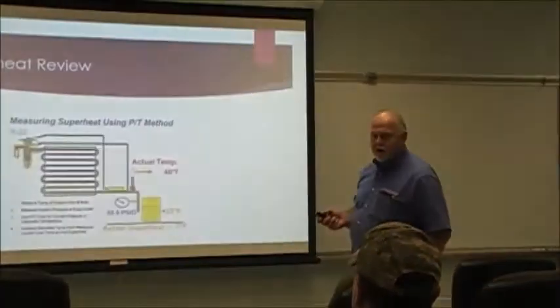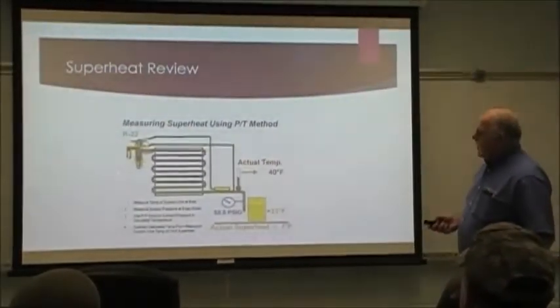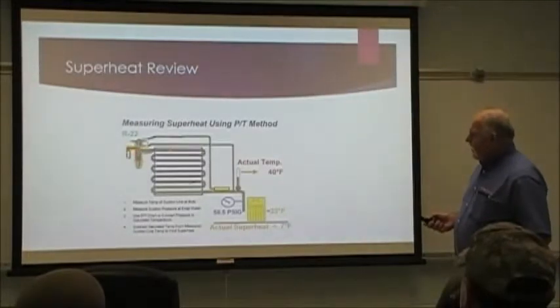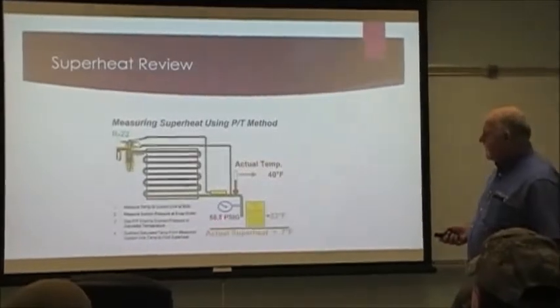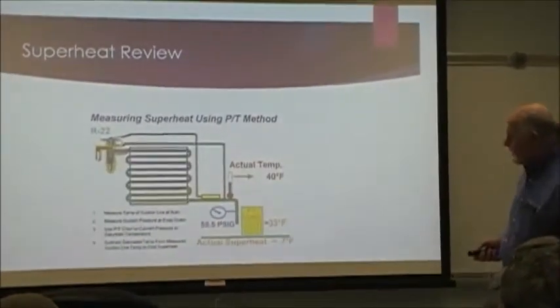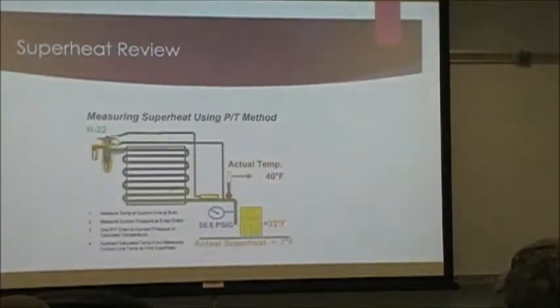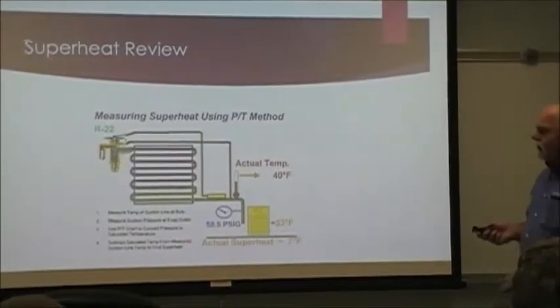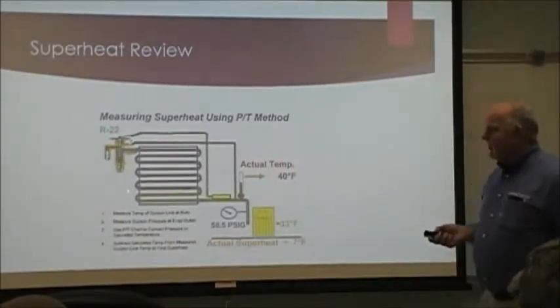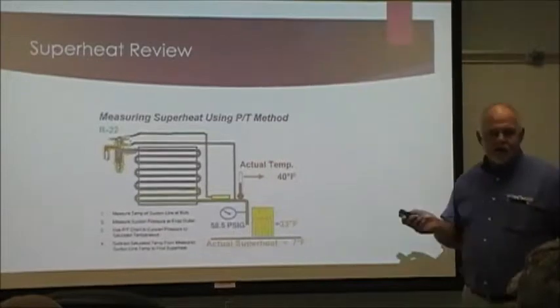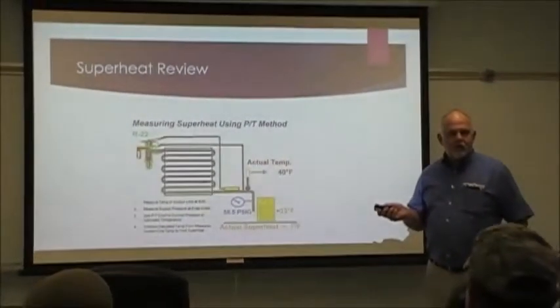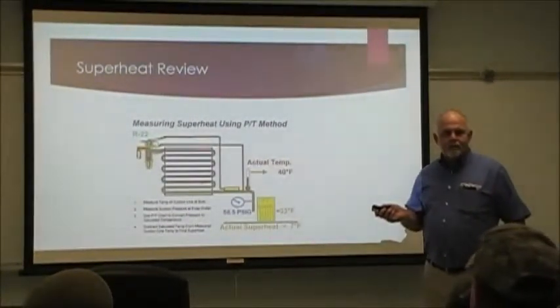Number two, to improve the efficiency of the coil, because we maximize the use of the coil. Because look what happens right here, and this is R22, and I know we don't use that anymore, but it comes out of the expansion valve right here, and it's a mixture of low pressure liquid and refrigerant. It's 58.5 pounds right there, which is, they say, and I'm going to take them at their word, 33 degrees. Do you know what I'm talking about when I say the saturated suction temperature is 33 degrees on that coil right there? Does everybody understand that?